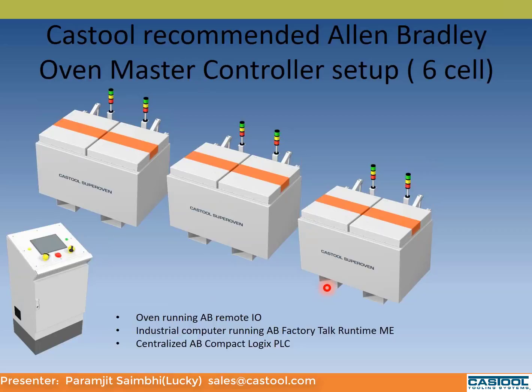So here we're showing you ovens. Basically, what we recommend if we're going with Allen Bradley is each cell will have remote I/O, so remote I/O for cell oven 1, 2, 3. And then everything connects to a centralized PLC. So you'll have a CompactLogix PLC running in the master controller connecting to the touchscreen. This is where you would be running FactoryTalk runtime software. We could also put the Allen Bradley PanelView Plus screens as well, but that is where you have to specify at the time of order, so we can build the right system for you.